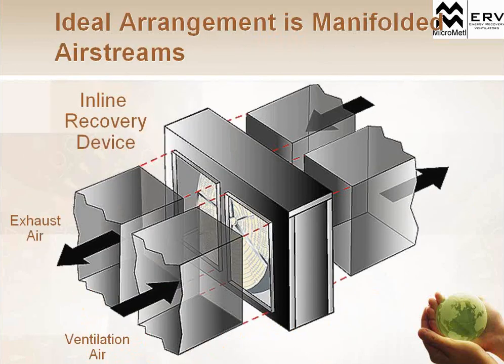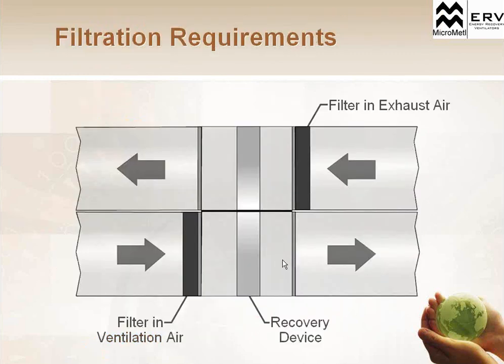So we talked about the wheel itself. Let's talk about the arrangement of an ERV, because this is also critical when we're installing an ERV in a system. When we put these airflows together, an inline recovery device, meaning that we're taking the supply and return airflows next to each other with an inline device between the two, is the most common application of the ERV.